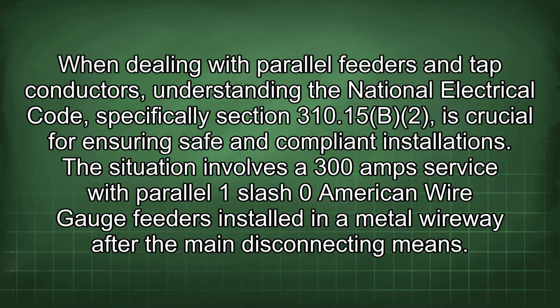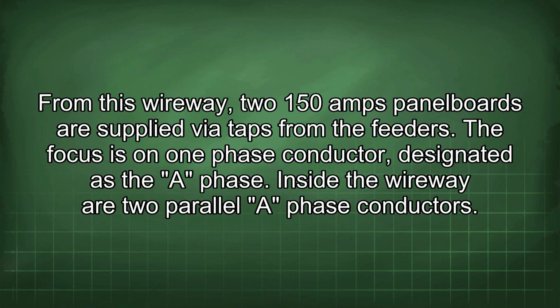When dealing with parallel feeders and tap conductors, understanding the National Electrical Code, specifically Section 310.15(B)(2), is crucial for ensuring safe and compliant installations. The situation involves a 300 amp service with parallel 1/0 American wire gauge feeders installed in a metal wireway after the main disconnecting means. From this wireway, two 150 amp panel boards are supplied via taps from the feeders.